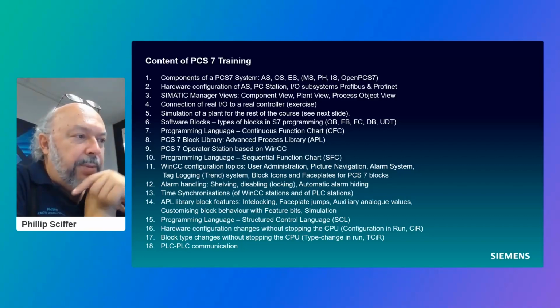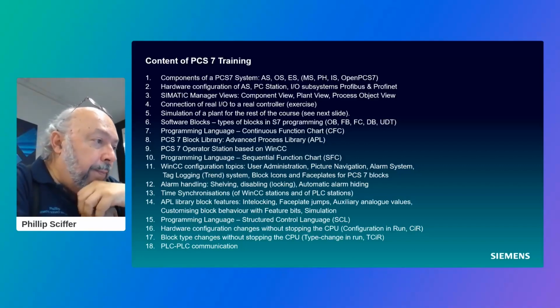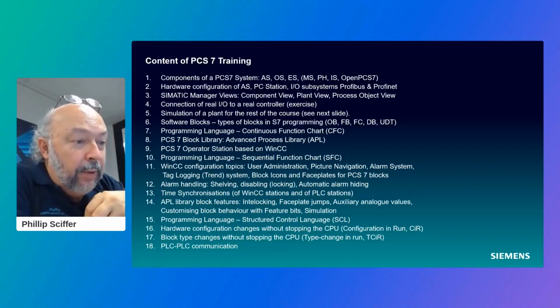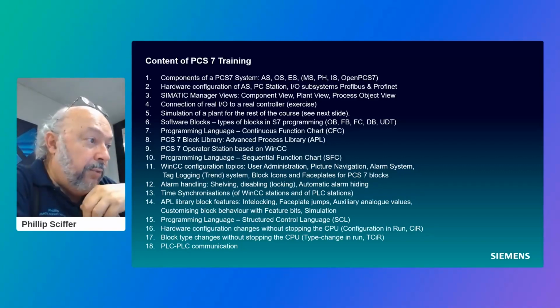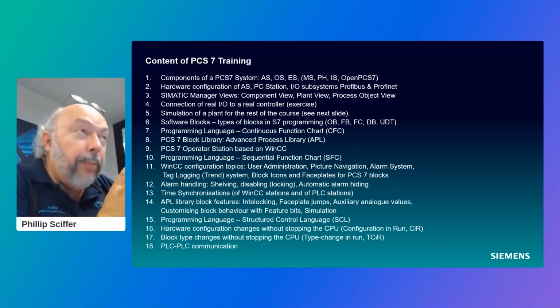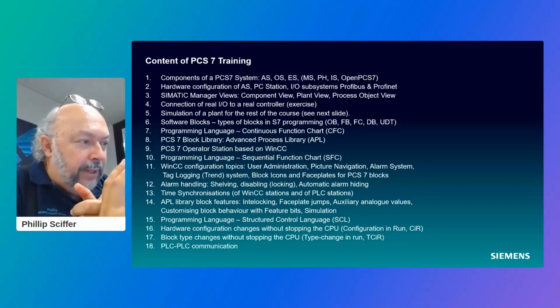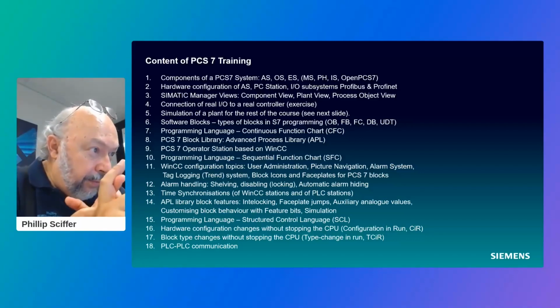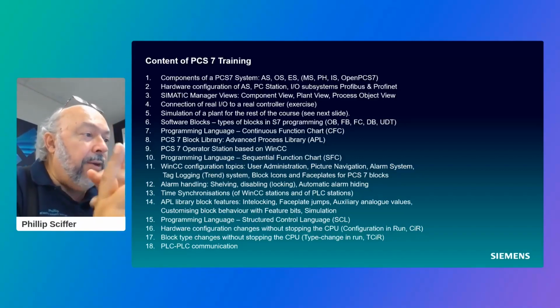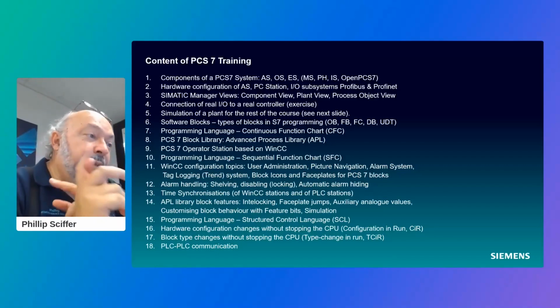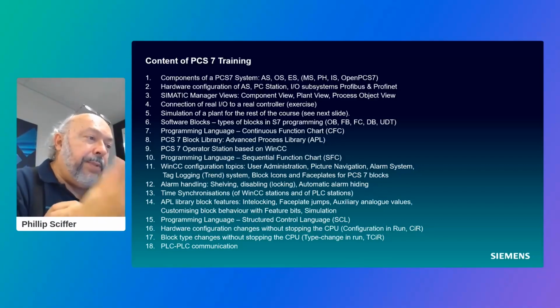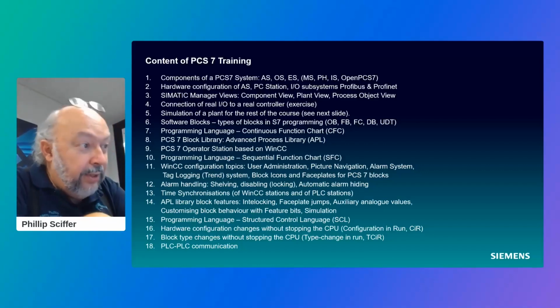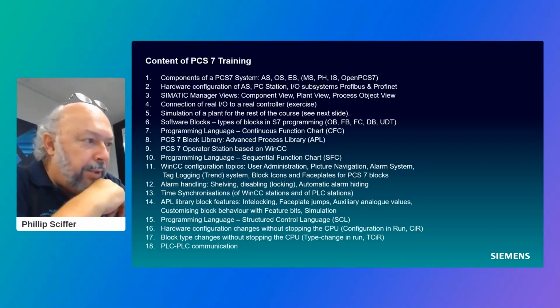We look at block icons and faceplates for the PCS7 blocks. For our PCS7 library blocks, so for the motor or valve, we supply a little graphic object that can be placed on the WinCC screen, automatically placed on the screens, automatically dynamized, so that when the PLC block changes state, WinCC changes to show you what's happening. And a faceplate, that's called block icons. Click on a block icon in runtime, and it pops up a faceplate, which is like a dialog box on the screen, where we get considerably more information about what's happening with that block, and we're able to control the block, start and stop the motor, and change set points for PIDs and things.